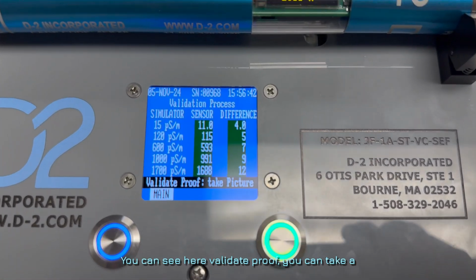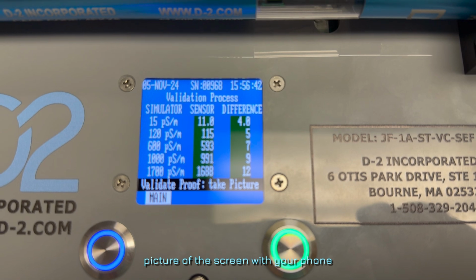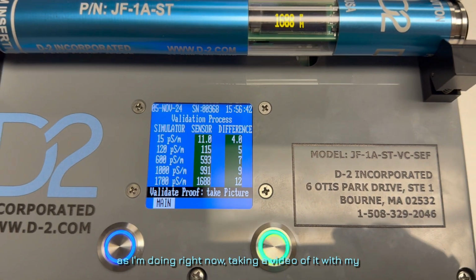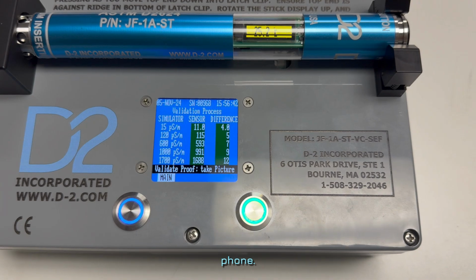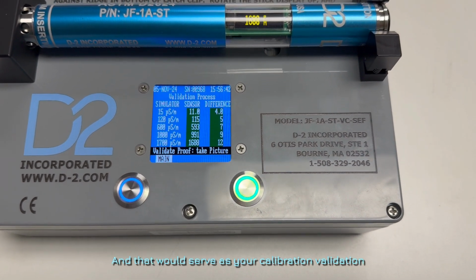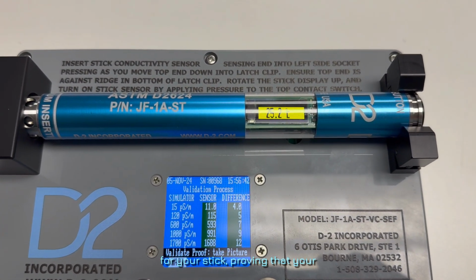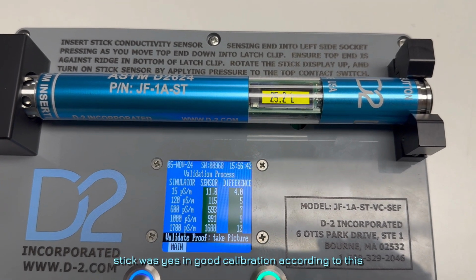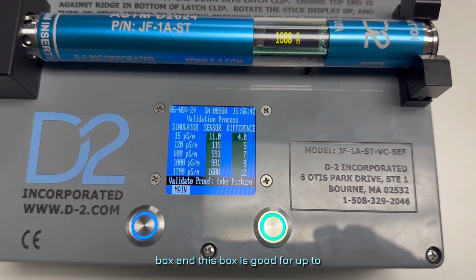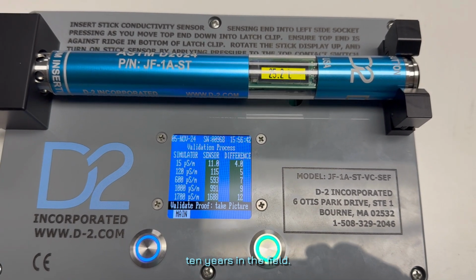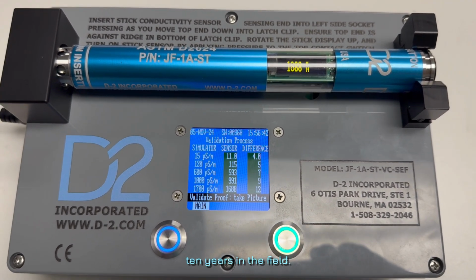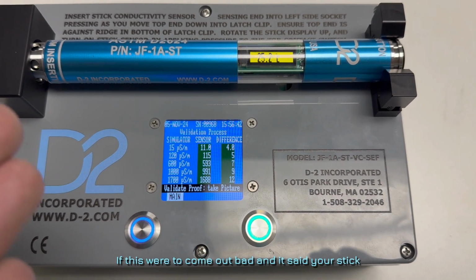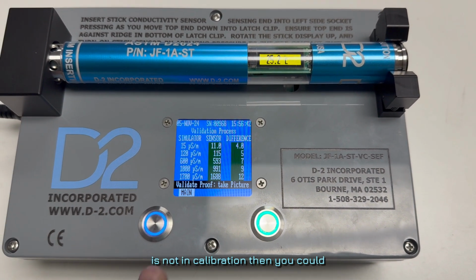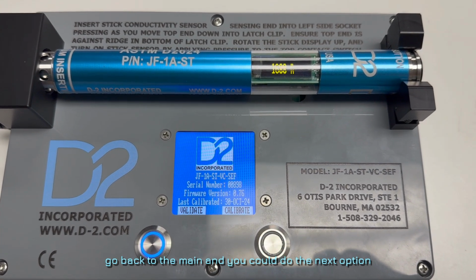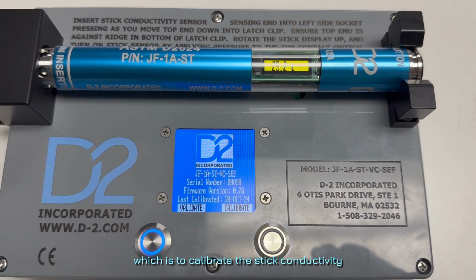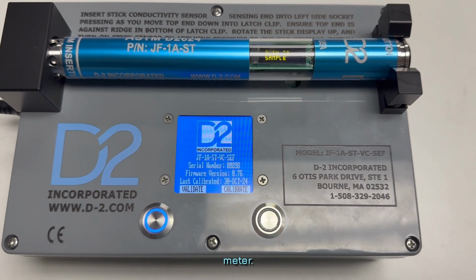You can see here, validate proof. You can take a picture of the screen with your phone, as I'm doing right now, taking a video of it with my phone. And that would serve as your calibration validation for your stick, proving that your stick was, yes, in good calibration according to this box, and this box is good for up to 10 years in the field. If this were to come out bad and it said your stick is not in calibration, then you could go back to the main and you could do the next option, which is to calibrate the stick conductivity meter.